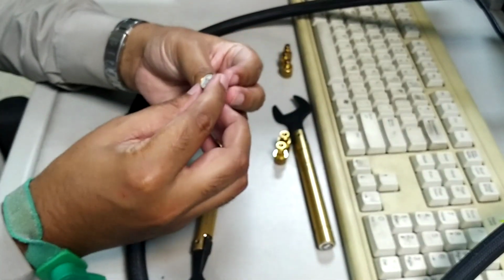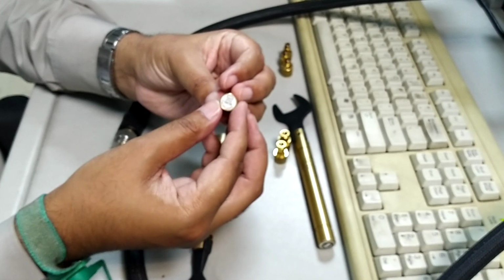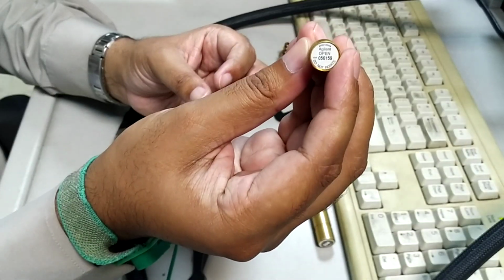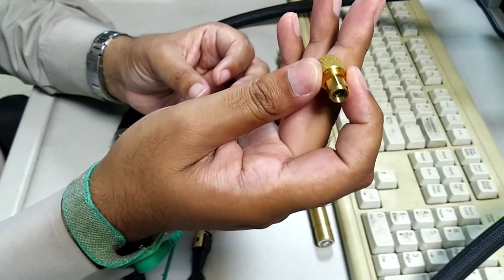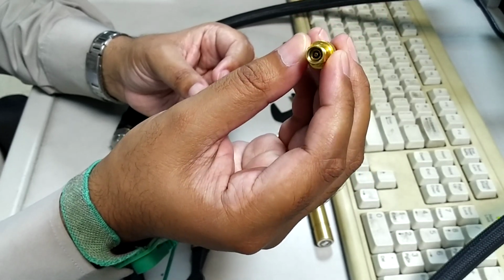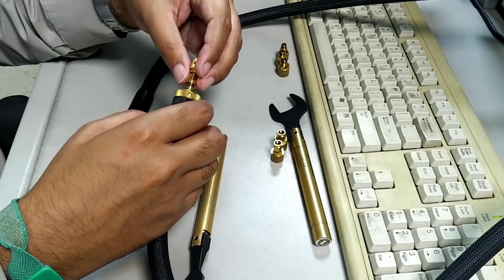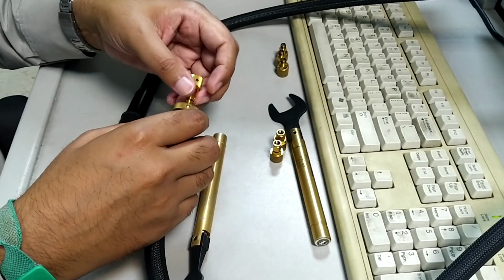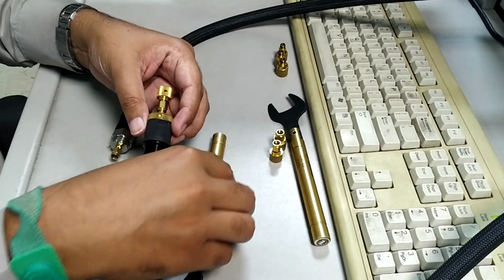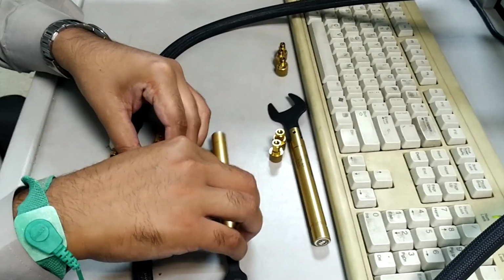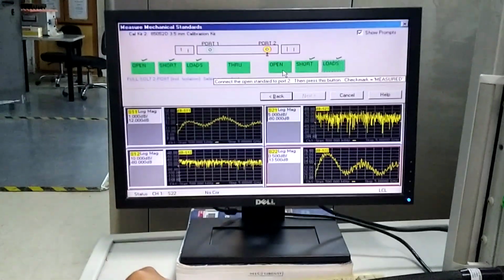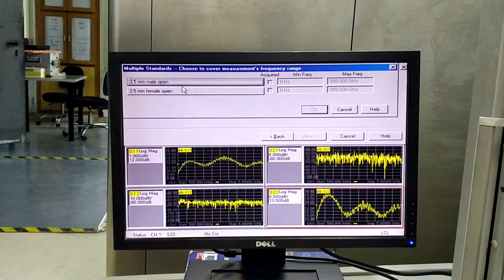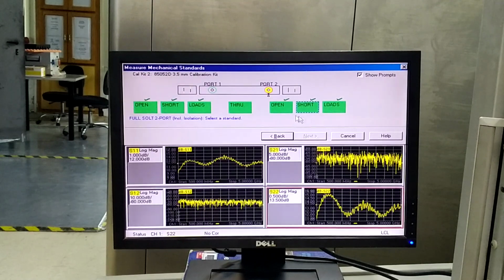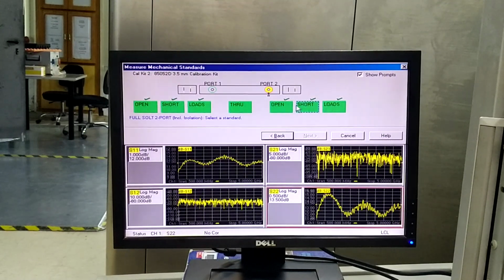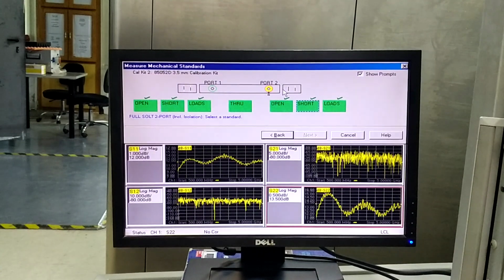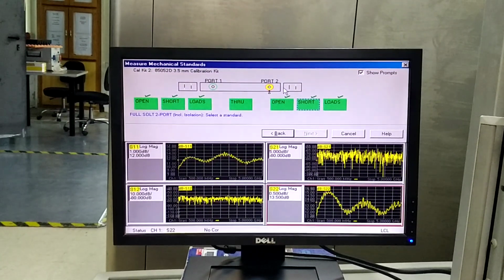The last one port calibration standard I have is an open standard, and you can see here, this is a male open standard with a pin inside. Now I use this standard with the cable and perform the measurements. If you see the screen, I click the open standard, open to port 2. Okay, this is a 3.5 mm male open. I select here, I press OK. So now you can see all the one port standards have been connected at port number 2, and the measurements have been saved. Now the next step will be to perform a through connection.